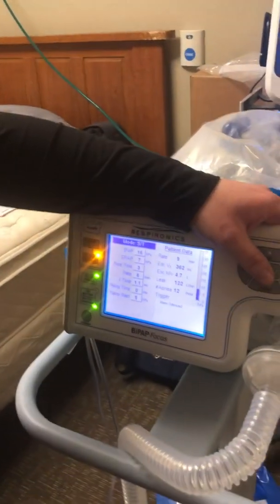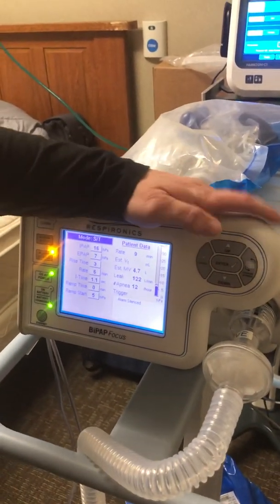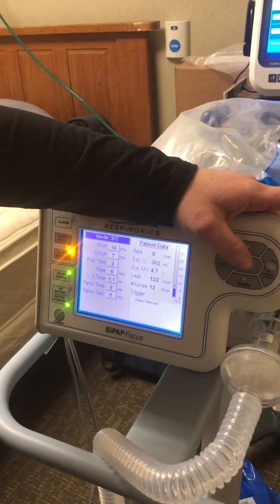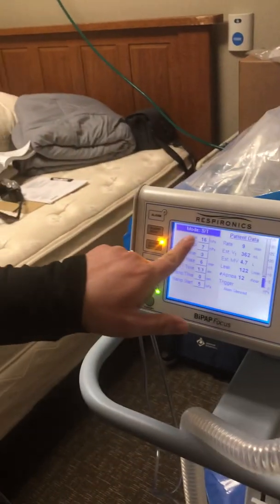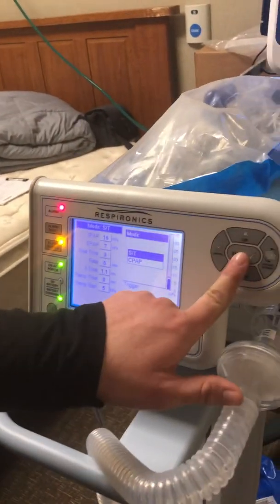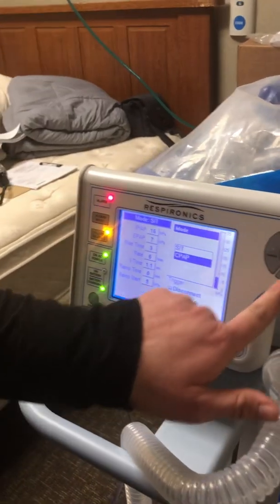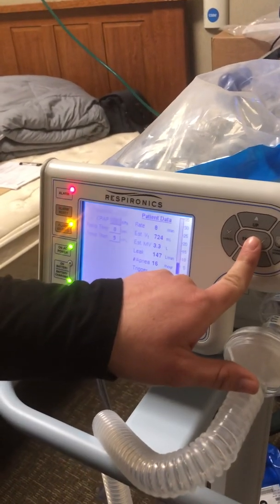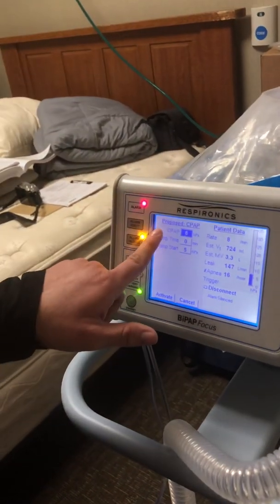If you want to change it to like a CPAP mode for a continuous flow, so you'll hit the enter, so make sure that's highlighted, the blue, hit enter, and you'll hit your down arrow to CPAP and hit enter there. So here we have our CPAP.